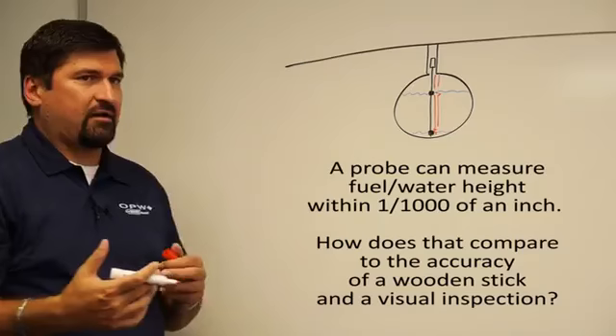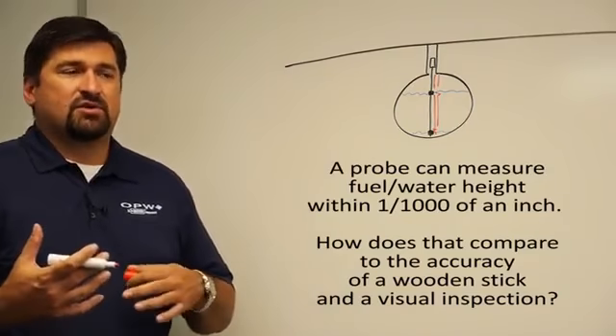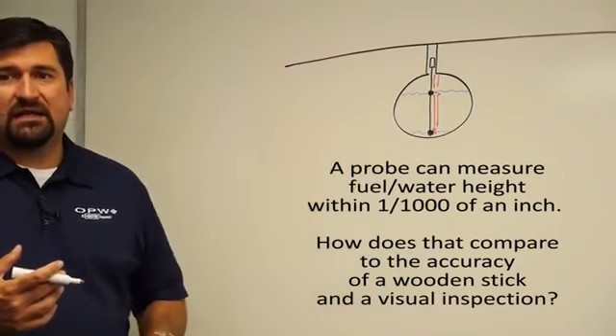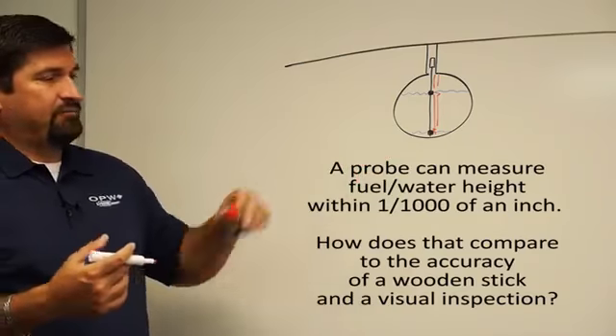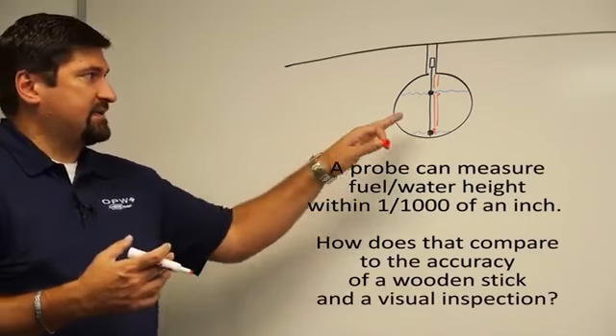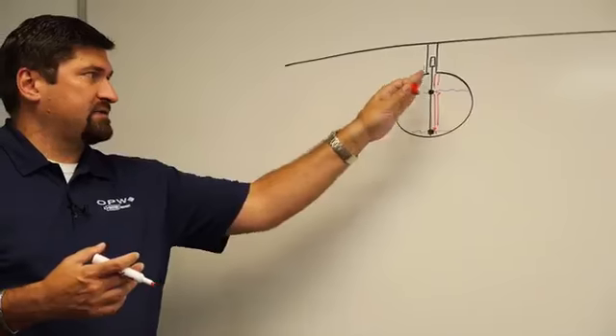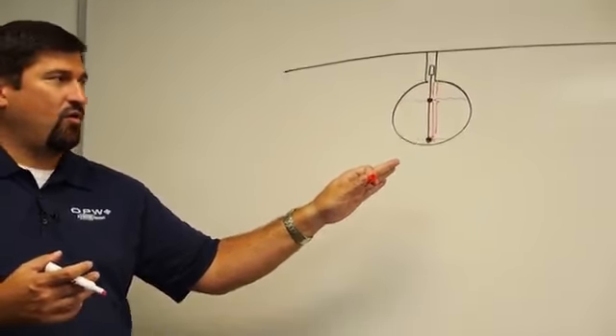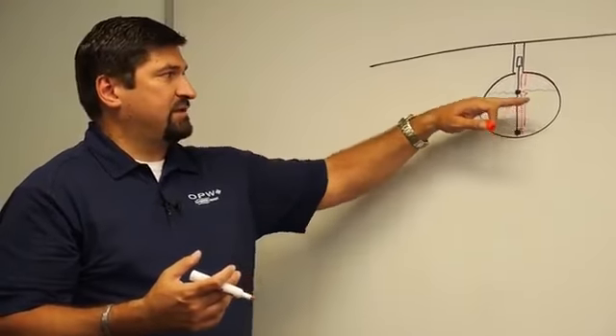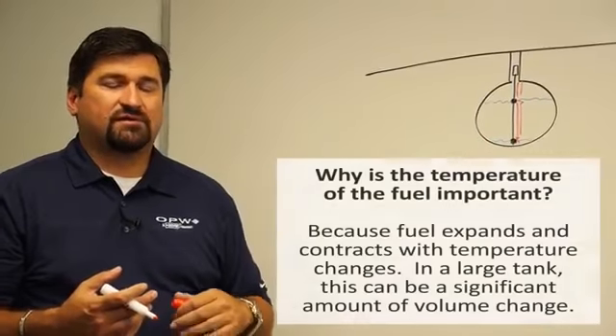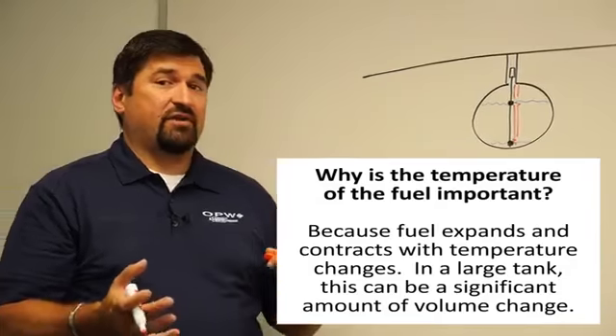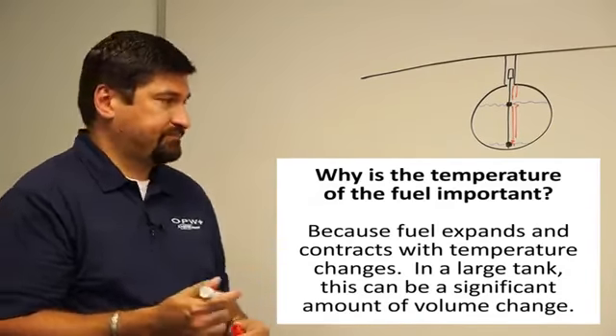And these probes are accurate to 1/1000th of an inch. So I can tell you very accurately what's inside that tank. Now, where it comes into play is that there's also temperature readings in 5 positions along that probe. So I can actually give you net corrected volume by measuring the temperature of that product at multiple levels inside the tank and actually giving you gross and net product volume.